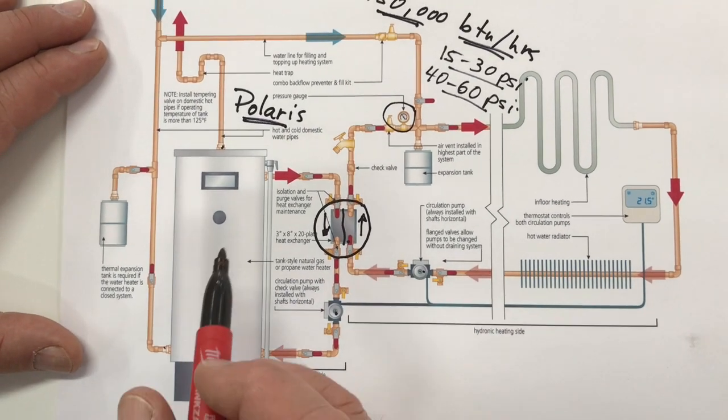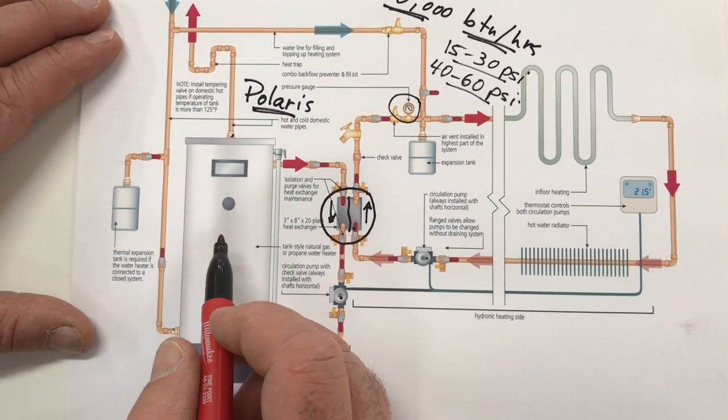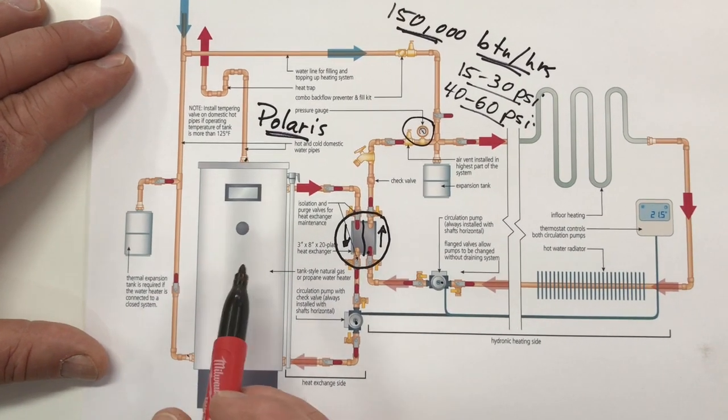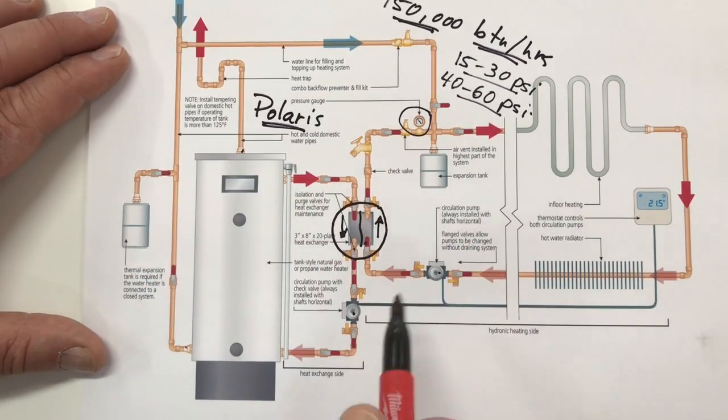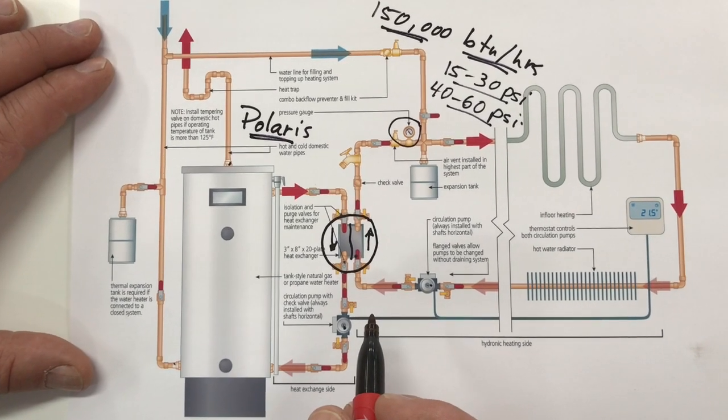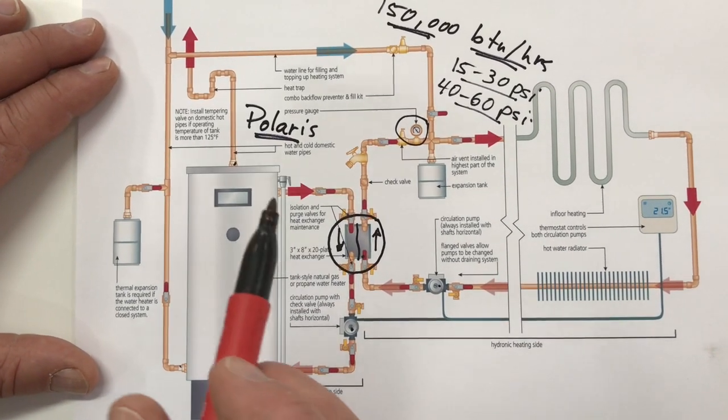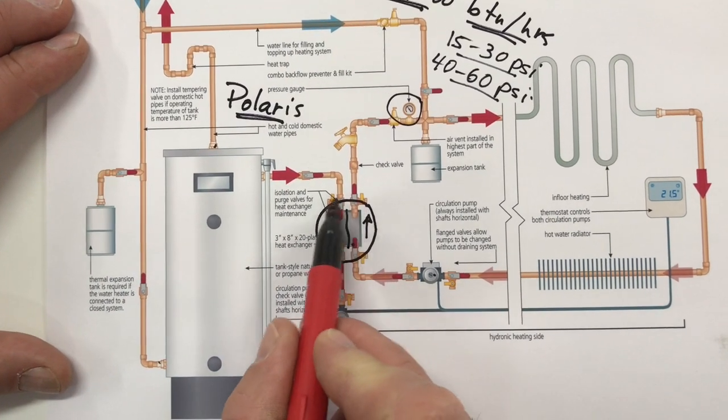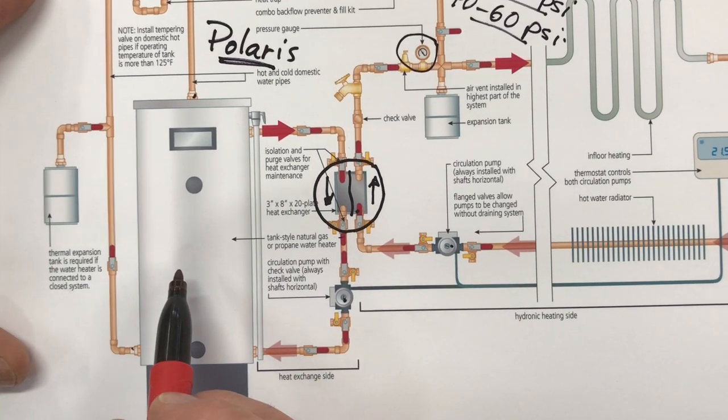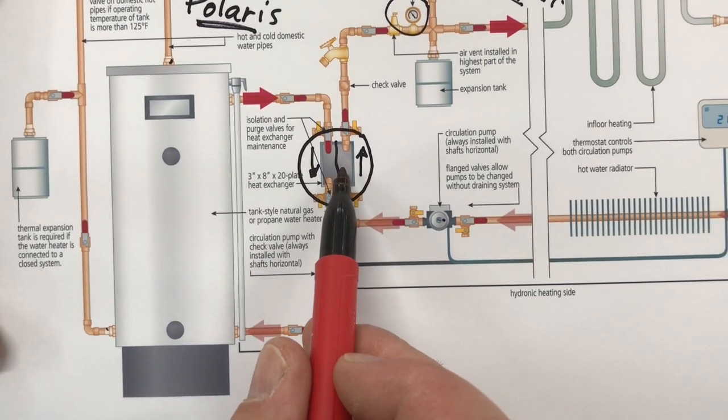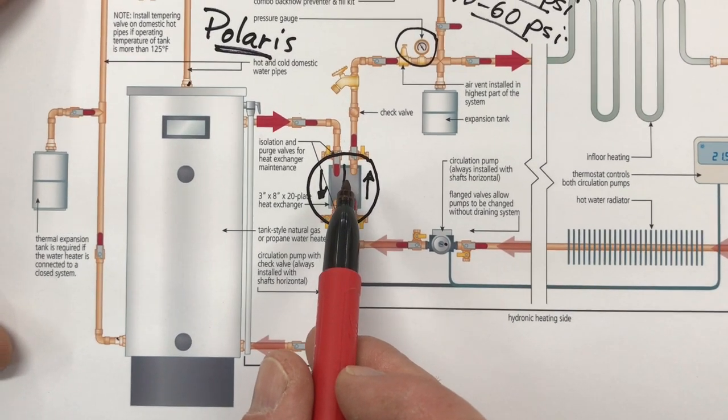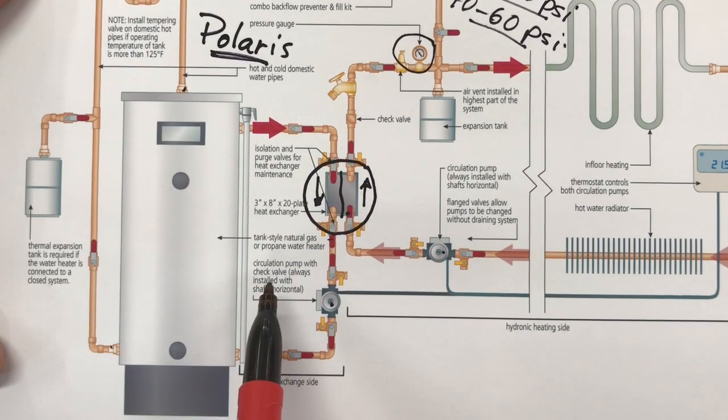Now another reason you'd want to use a tank style heater is because it's just simpler. You've got one appliance and it'll serve you all year round for domestic hot water, tapping in as needed during the heating season for heating. If you go with the simple installation and you eliminate the need for a heat exchanger, maintenance is also lower too because with any kind of a boiler you've got a built-in heat exchanger that will form scale on the domestic side of the system.